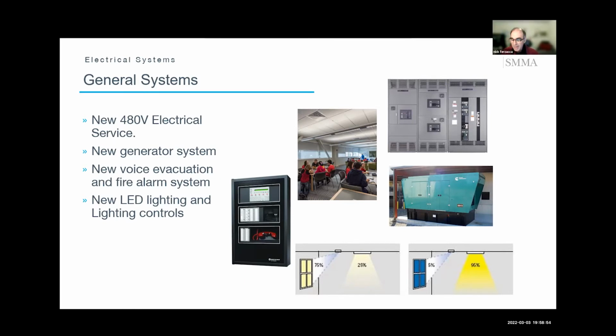The controls are very heavily driven by the codes, and as Martine suggested, we're looking at the proposed Mass amendments to the energy code and trying to build those into the design now. In general, you're going to have automatic lighting controls throughout the building, which I think will be a point of conversation with the staff. There's not too much flexibility we have in that. In order to meet the code, we have to provide automatic occupancy sensors in classrooms, daylight sensors at the perimeters. We'll certainly want to get the staff comfortable with how that system operates, but the lighting controls have become very robust these days.